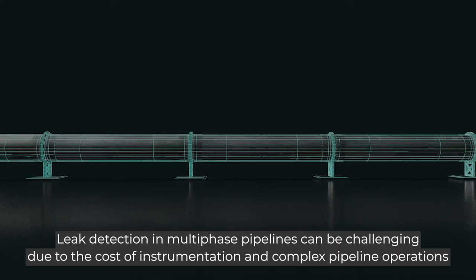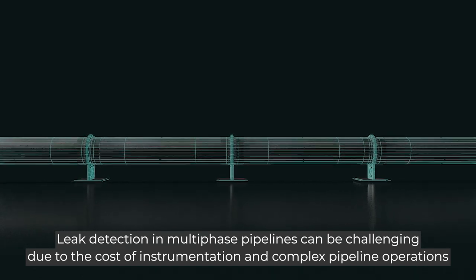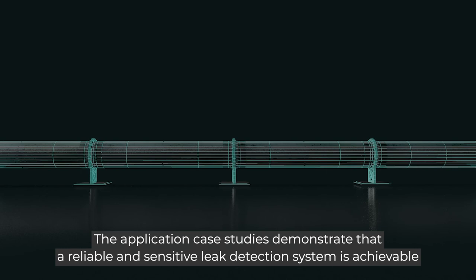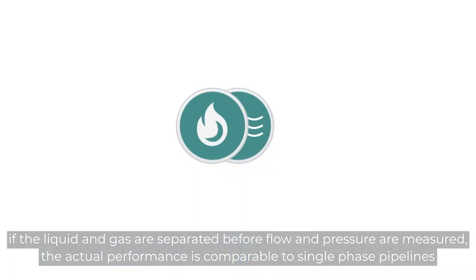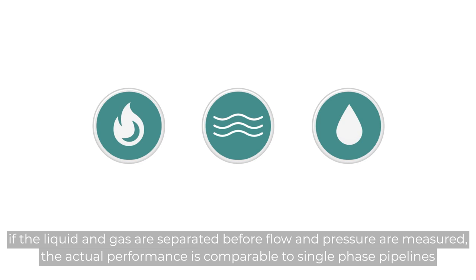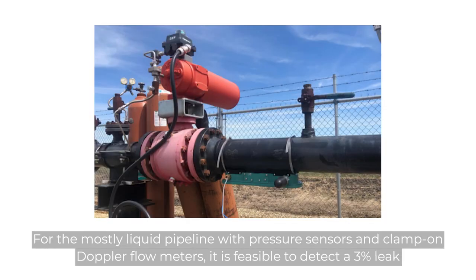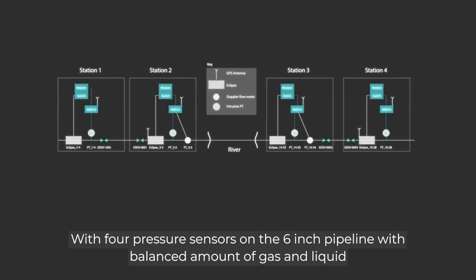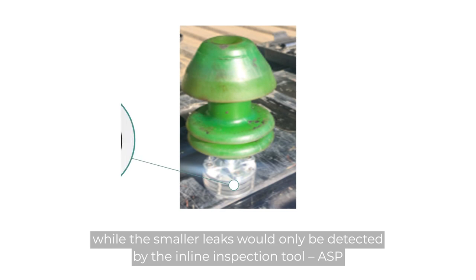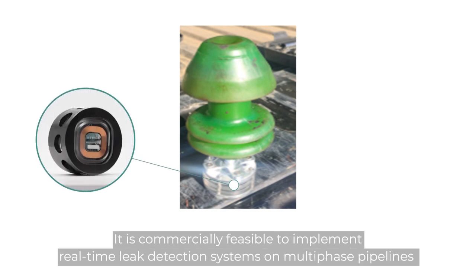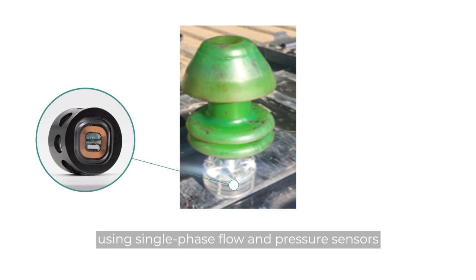Conclusions. Leak detection in multi-phase pipelines can be challenging due to the cost of instrumentation and complex pipeline operations. The application case studies demonstrate that a reliable and sensitive leak detection system is achievable. If the liquid and gas are separated before flow and pressure are measured, the actual performance is comparable to single-phase pipelines. For the mostly liquid pipeline with pressure sensors and clamp-on Doppler flow meters, it is feasible to detect a 3% leak. With four pressure sensors on the 6-inch pipeline with balanced amount of gas and liquid, a reliable online leak detection system is achievable using the pressure wave system, while smaller leaks would only be detected by the inline inspection tool ASP. It is commercially feasible to implement real-time leak detection systems on multi-phase pipelines using single-phase flow and pressure sensors.